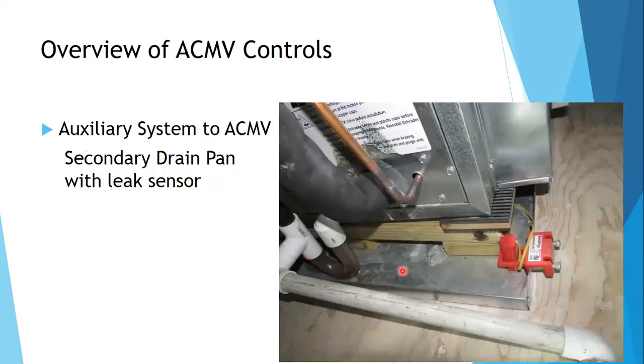So first, the secondary drain pan for your air handling unit and fan coil unit. To prevent spill, there will be times that the equipment will fail. And the problem is you wouldn't know which equipment will fail, especially if this equipment is installed overhead. So when an equipment fails, to prevent it or to detect this failure early, you put a secondary drain pan. When water is leaking from the equipment, your secondary drain pan will capture it, and the secondary drain pan has a water leak sensor. So this water leak sensor will sense that there's water and send an alarm telling that there's something wrong with this specific unit. So secondary drain pans are important in installation, especially for overhead units.